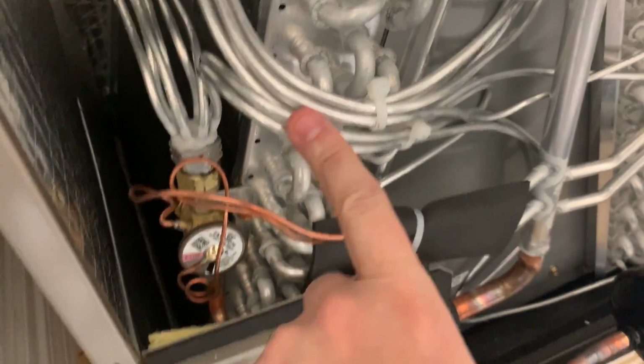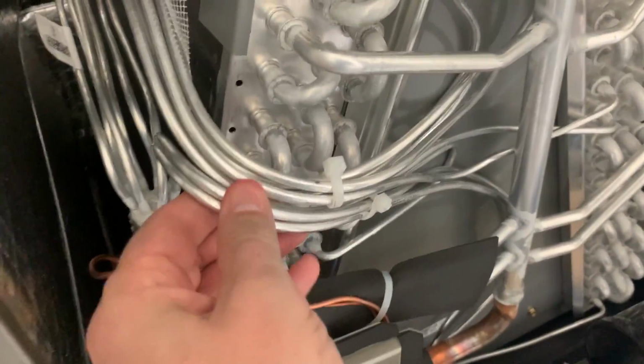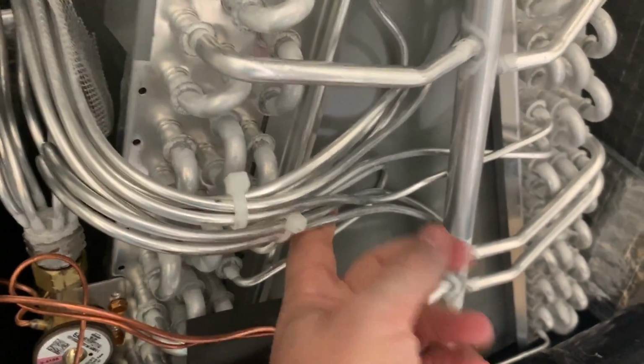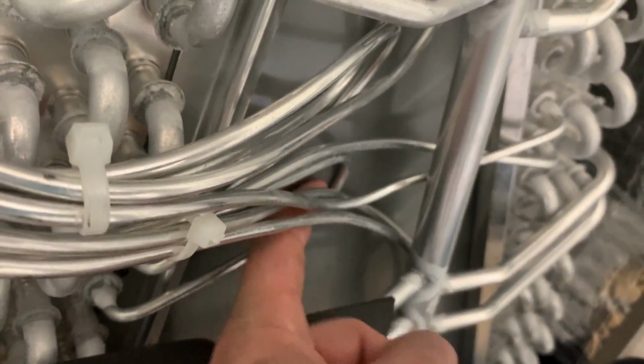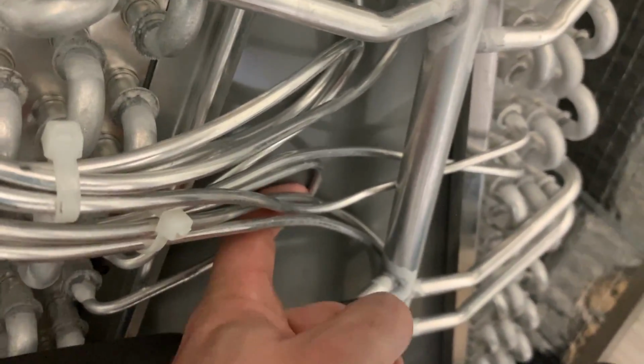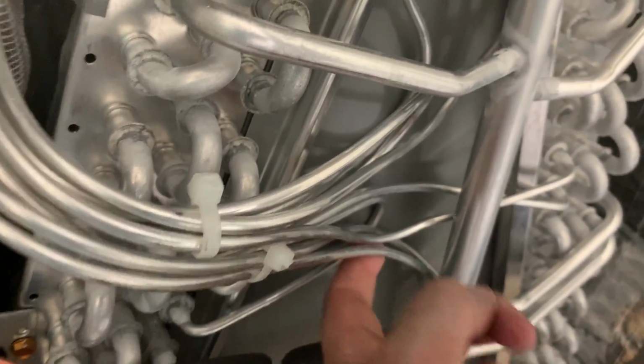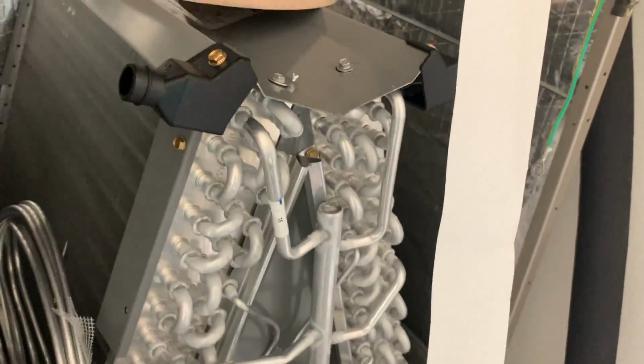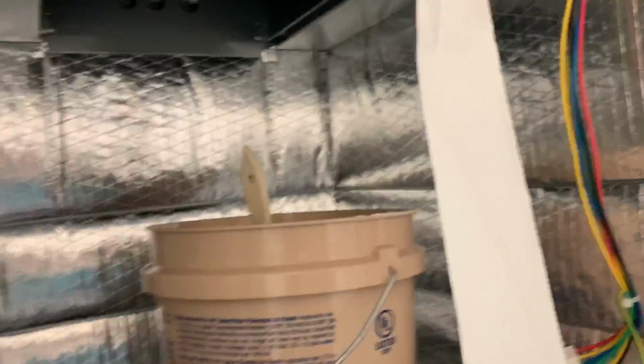You can see you have the all aluminum evaporator coil, and one thing I always look at is just making sure that we're not going to have any vibration that could result in something rubbing where it shouldn't, like right there. That's a little bit of a concern point, so I'm going to make sure that we separate that and put a little foam tape in there just to be 100% sure that we're not going to get any rubbing. The factory does a good job, but we have to double check everything they do as well, just to make sure it's all good before we leave.